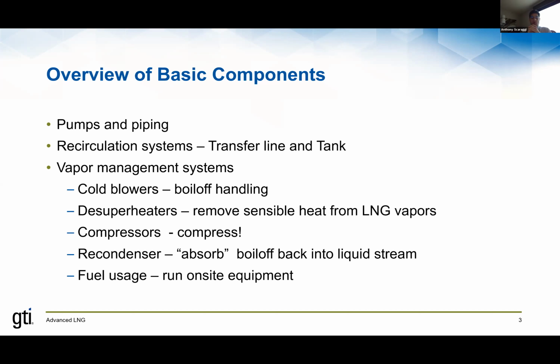And you also use compressors to take boil-off gas and bring it up in pressure to deliver it someplace else. So as I said earlier, LNG is at about atmospheric pressure, which is a very, very low pressure compared to typical pipeline pressures where gas would be delivered into. So if you wanted to take that boil-off gas and put it into a pipeline, you'd need a very large compressor to compress it up from, let's say 2 psi up into pipeline pressure, which could be 1440 psi. So very, very large compressors at LNG facilities even on the gas side, meaning on the cold side.